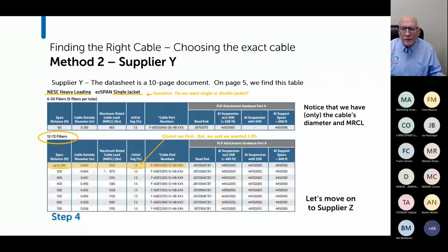And notice that the only technical information I have is a diameter and an MRCL. That's not enough information to do sag and tension calculations, just saying. So let's move on to supplier Z.